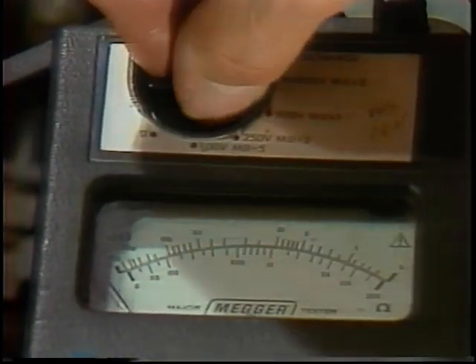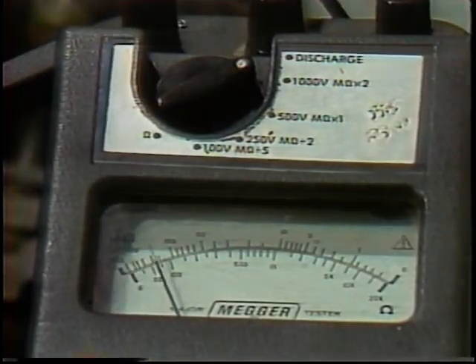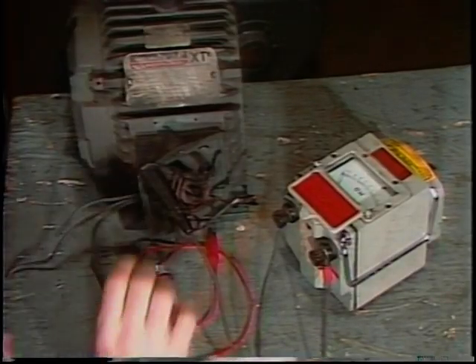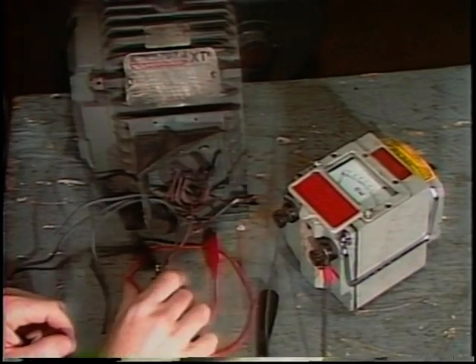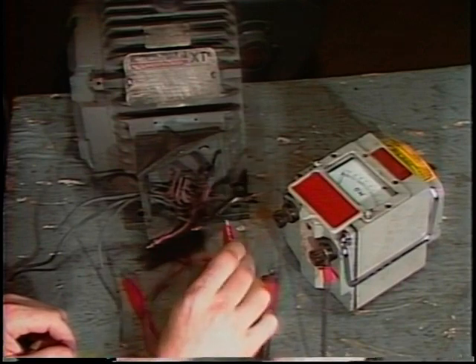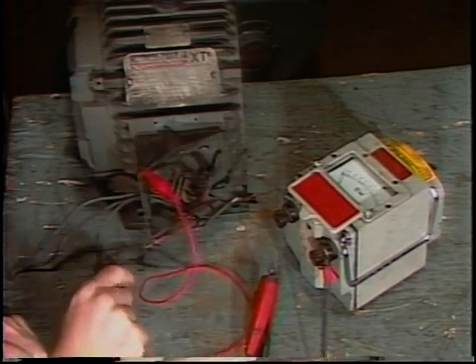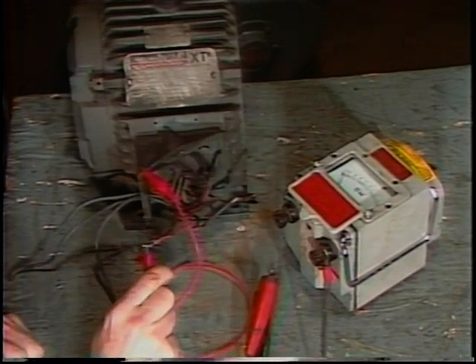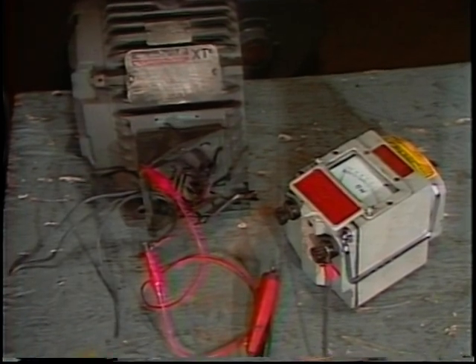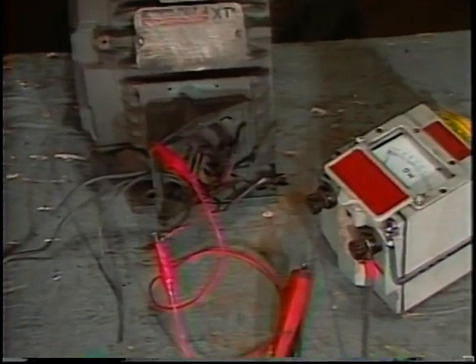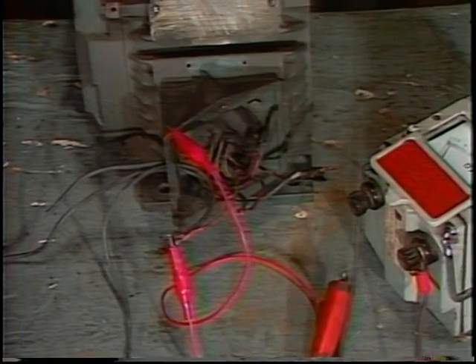Taking a megohmmeter reading charges the insulation like a capacitor. It should be allowed to discharge. If your meter does not have a discharge feature, carefully short together the points where you had the probes attached. Complete discharge may take some time. The general rule is to leave the short in place at least 4 times as long as the voltage was applied by the megohmmeter.